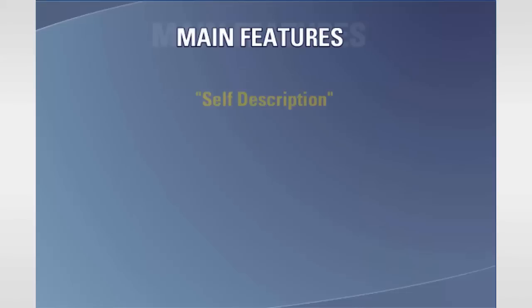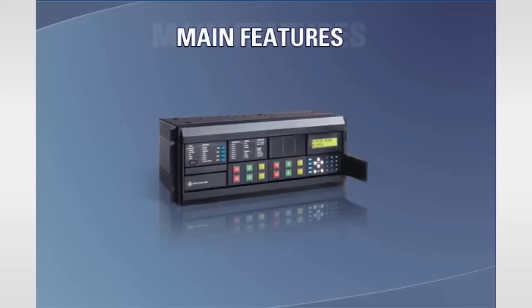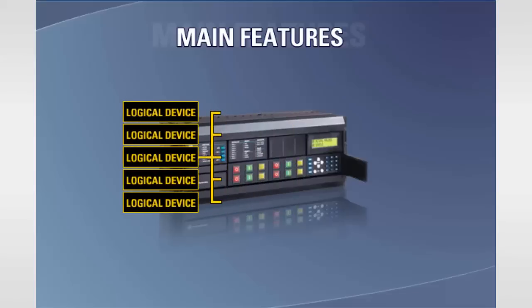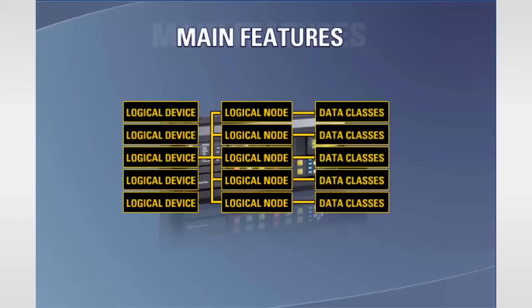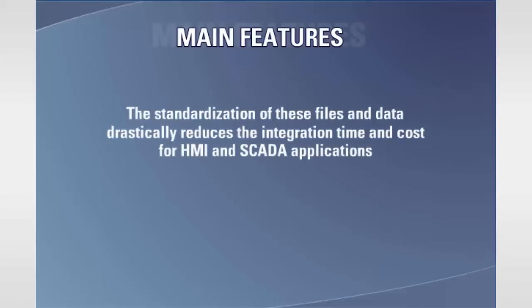IEC 61850 also supports what is termed as self-description. This refers to the ability of a device to be browsed to determine what data is contained within it. Each physical device, such as a relay, may contain one or more logical devices. Each logical device may contain one or more logical nodes, such as a circuit breaker or transformer. Each logical node contains a predefined set of data classes which contain data. The logical node data can be browsed, similar to using a finder or explorer to search computer files. The standardization of these files and data contained within the relays drastically reduces the integration time and cost for HMI and SCADA applications.